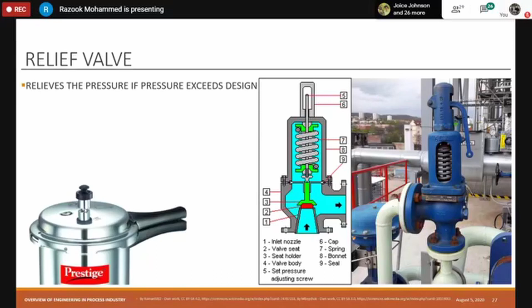The simple example we see in everyday life is a pressure cooker. As we said in the pressure cooker example, we are increasing the boiling point temperature by increasing the pressure. So we are maintaining the pressure by keeping a weight-loaded relief valve on top of the lid. The difference is, in an industry, mostly you will find spring-loaded relief valves because the force requirement is huge. It cannot be achieved by a weight. But in our home situation, a weight is enough because we are only increasing the pressure from 1 bar to 2 bar G. That is required only. So a small weight is adequate for achieving the purpose. So this is the pressure relief valve.